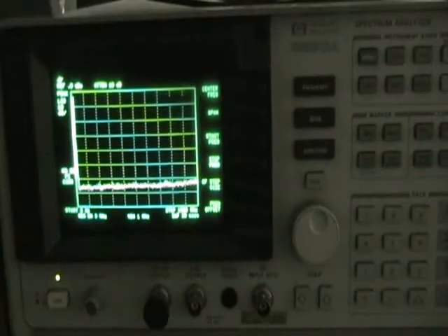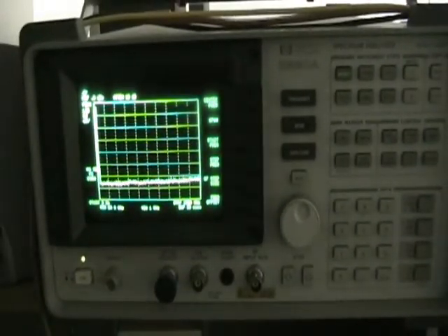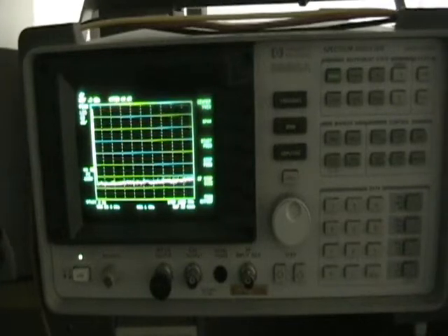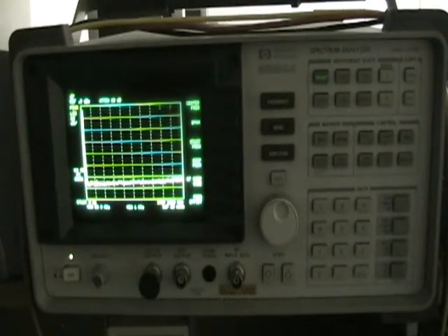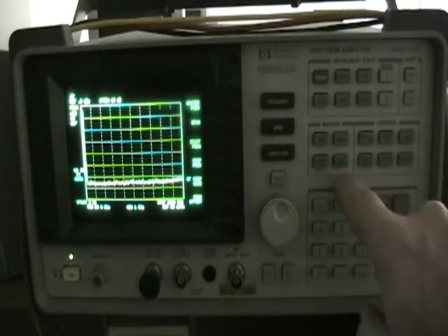We are looking to have a signal of 100 kilohertz and minus 10 dBm. So let's first set up the spectrum to display signals from 0 to 1 megahertz. There are many ways to do that, but this is by far the easiest way we have learned over the years. First thing, after pushing the green button, press peak search.